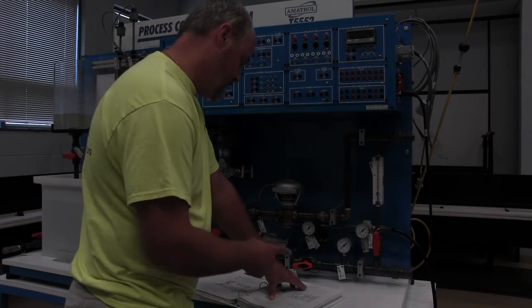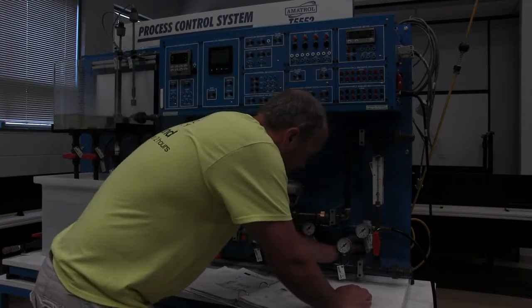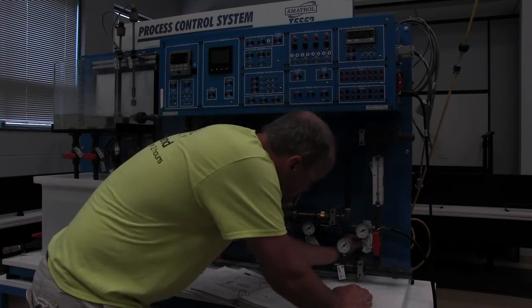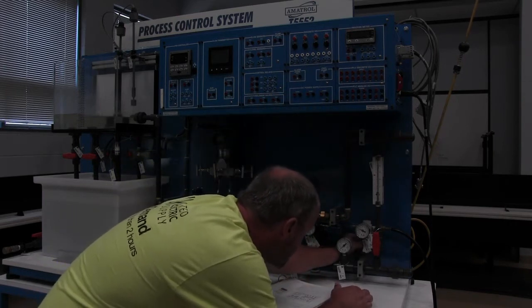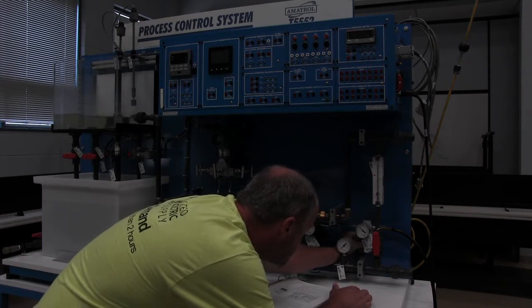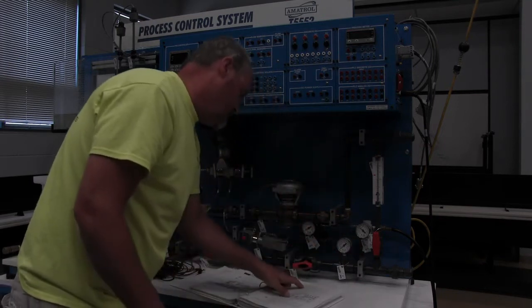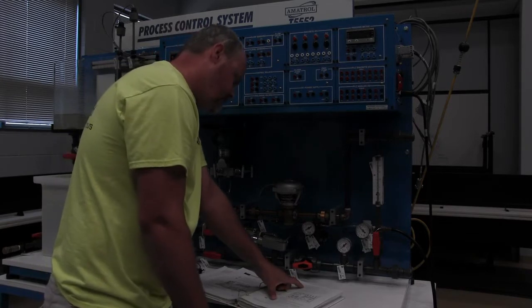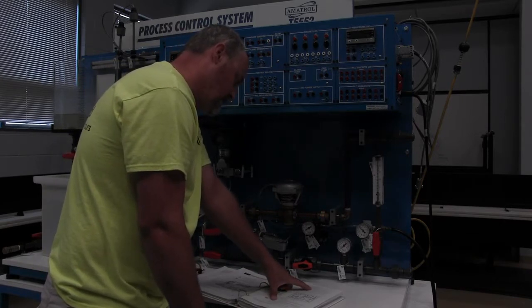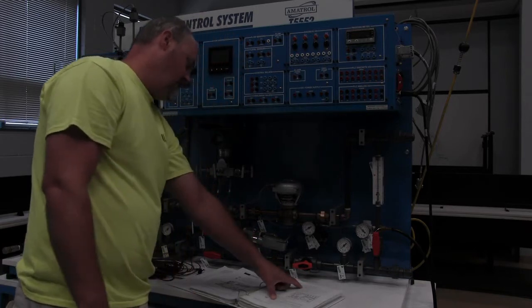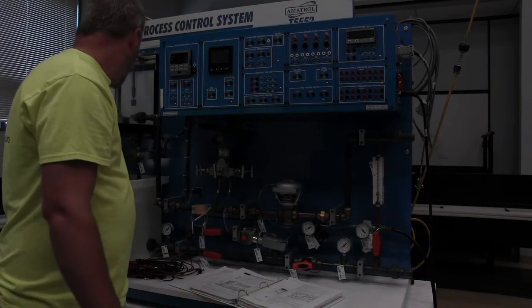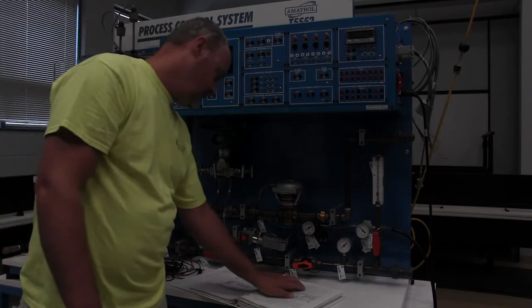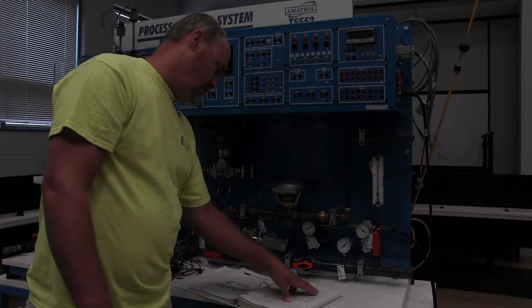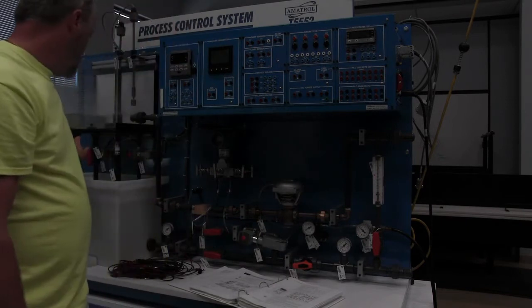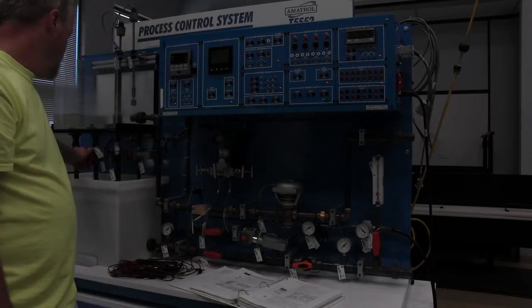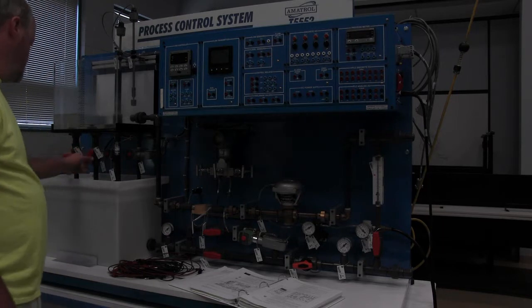We're going to set the regulator to 20 psi. So we have the regulator now set at 20 psi. Fully closed clockwise, the left side process tank manual drain, HV 300, which is closed. So I'll go ahead and drain this. Open the right side of the process drain approximately halfway. So now that we're drained, we'll go ahead and make this about halfway.